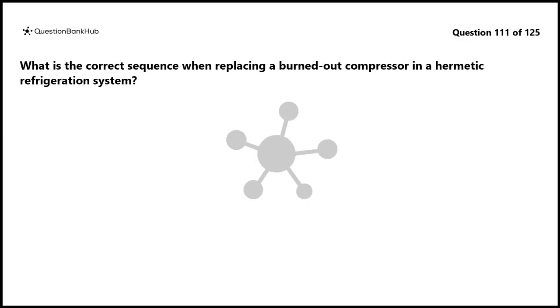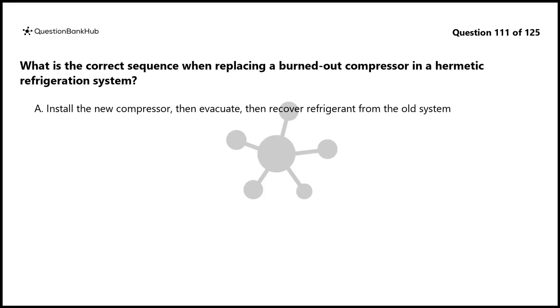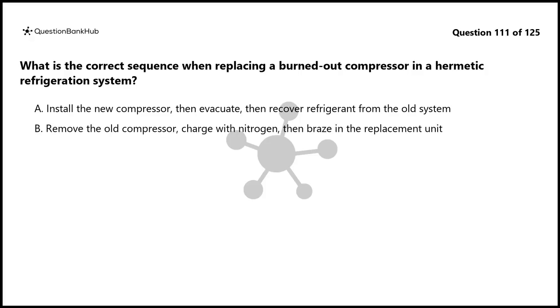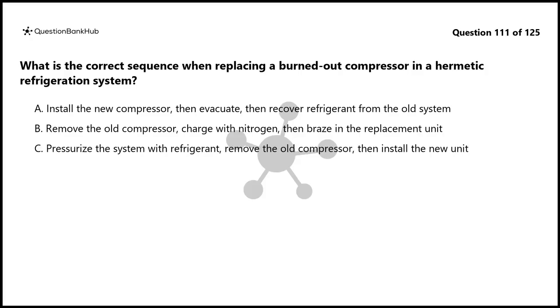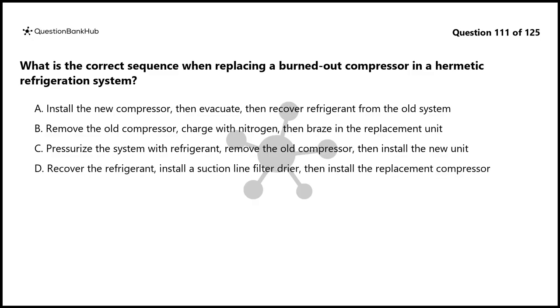Question 111. What is the correct sequence when replacing a burned-out compressor in a hermetic refrigeration system? A. Install the new compressor, then evacuate, then recover refrigerant from the old system. B. Remove the old compressor, charge with nitrogen, then braze in the replacement unit. C. Pressurize the system with refrigerant, remove the old compressor, then install the new unit. D. Recover the refrigerant, install a suction line filter dryer, then install the replacement compressor.